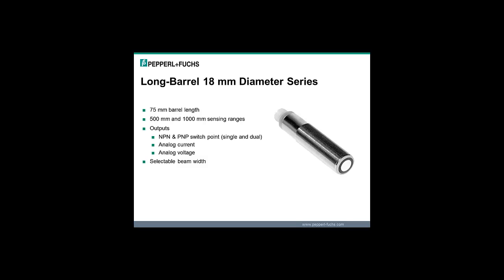But moving on, again, this longer barrel 18 millimeter diameter series, same outputs as we've discussed before with analog and switch point, but it's also got a selectable beam width, which can be nice. So by taking the teach input for the beam selector, you can make for a wide beam or a skinny beam. So you can customize this sensor without the use of software for applications where you might need something with a beam that's a little tighter, a little wider.